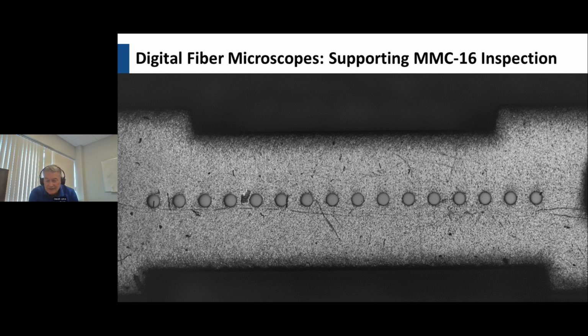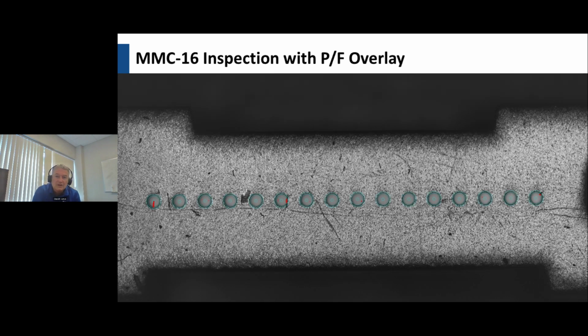The test and inspection industry has also been designing products to support this. There are a lot of very high quality digital microscopes on the market that will allow very good imaging, in this case, of an MMC-16. Looking at the overall connector itself, there's also obviously the IEC rules to actually do the analysis of each one of the end faces, to determine which ones pass and which ones fail.